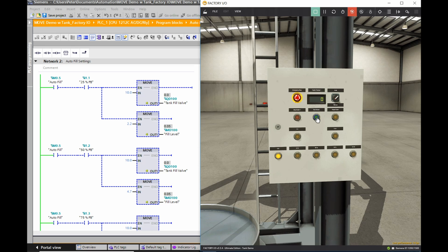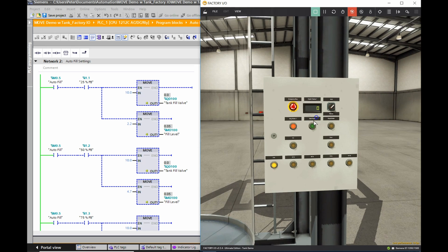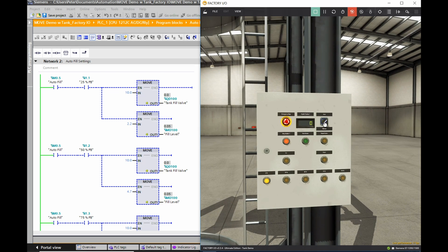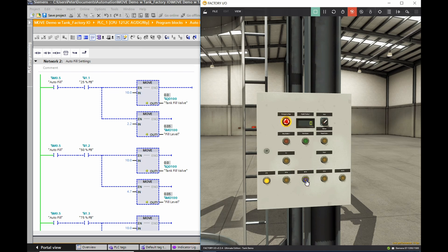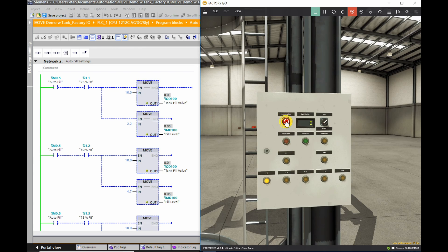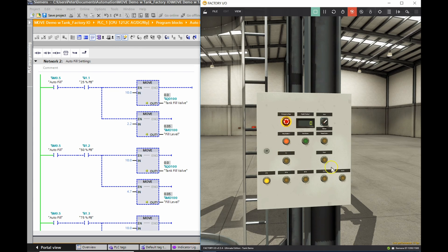When I'm in the E stop mode, then nothing works. Start push button doesn't work. This one will be able to change between auto and manual, but none of these other push buttons will work and nothing fills or drains when we're in an E stop mode. If I revert the stop back to its same spot, hit the reset, then I'm able to make use of each of these push buttons now. So we've seen it in the manual mode. Let's go to the auto mode now.